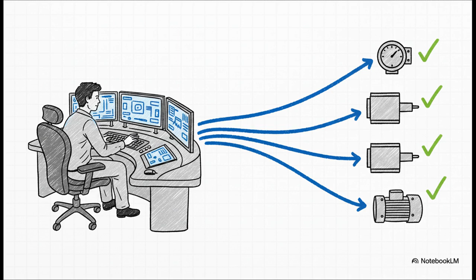And the benefits don't stop there. They keep paying off for the entire life of the plant. Because these devices are smart, they're constantly feeding back all this rich diagnostic data. This lets you do what's called predictive maintenance, basically fixing small problems before they become big, expensive shutdowns. Your technicians can troubleshoot problems from the control room, which saves them countless trips out into the field. And that's not just more efficient, it's a heck of a lot safer too.